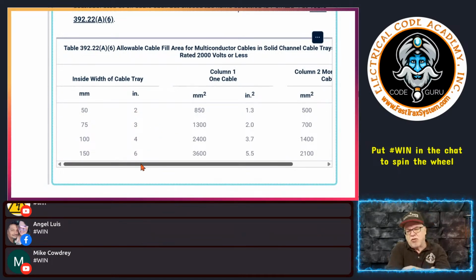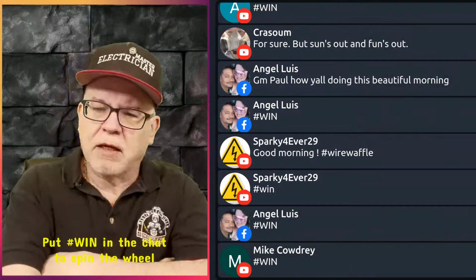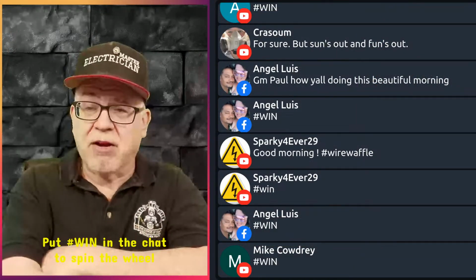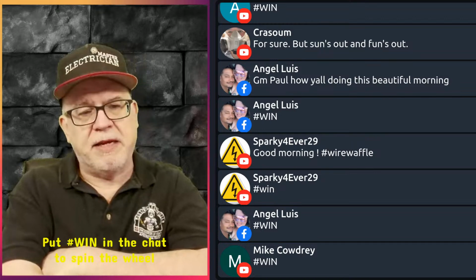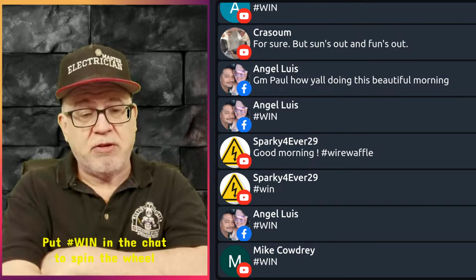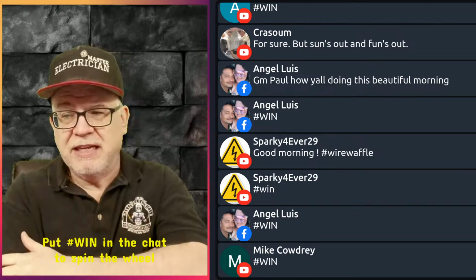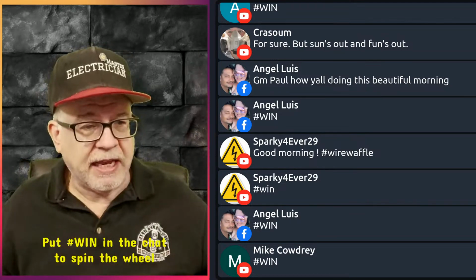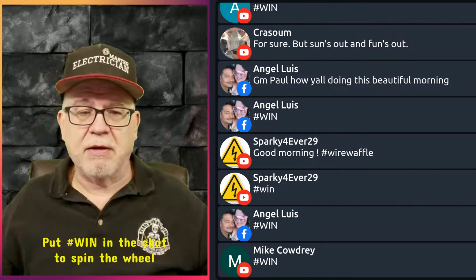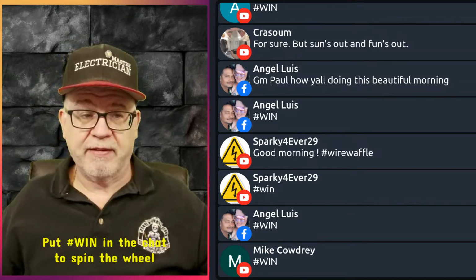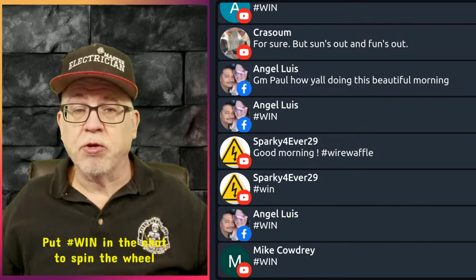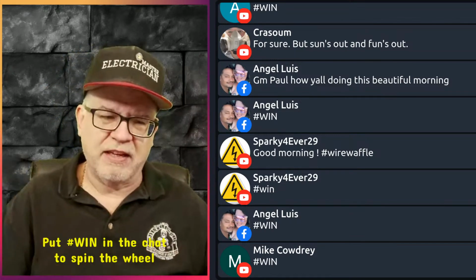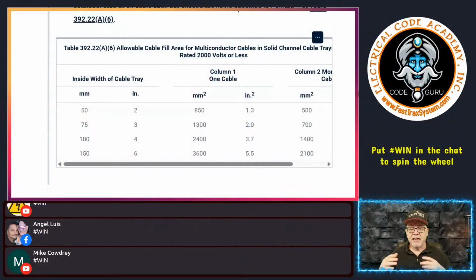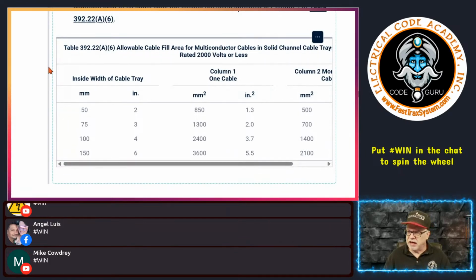If there's any larger than that, and I don't know the standards, by the way, for these types of trays. I'm not a cable tray guy to know their standards. But if they happen to make one that's larger, I would think that the manufacturer will give you the information, and you can utilize the information that the manufacturer gives you. Other than that, you're going to pull from these tables. Again, I'm not a cable tray manufacturer, but I am sure that they will give you more information than you care to want when it comes to cable trays. If you reach out to them, if it's something that doesn't really jibe with what's in the NEC, that type of thing. Just because it's not in the NEC doesn't mean they don't make it. Remember, this is a minimum safety standard. All right, so that's that.